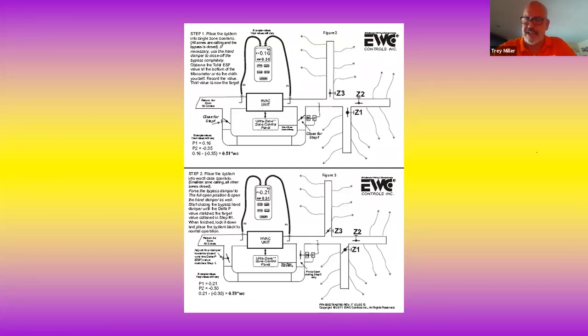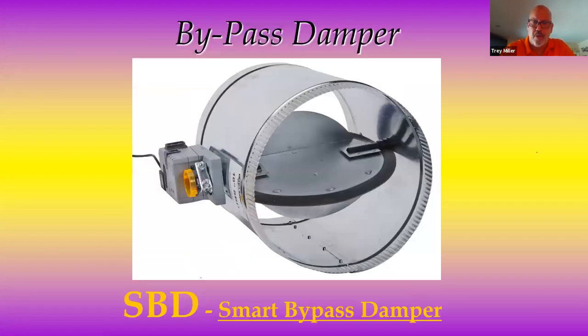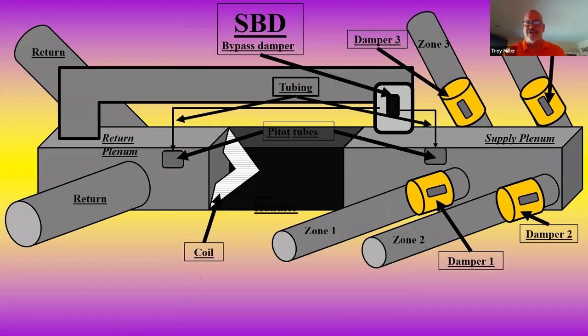The beauty of the SBD, guys, you don't need your $35 mechanic out there to balance the system out. You don't need him to pull his manometer out of his bag. You don't even need him to pull it out of his truck. You can have your installer push a button. Let me show you what we're going to do with the smart bypass damper. This is what we've got. We're going to have a call from all zones.